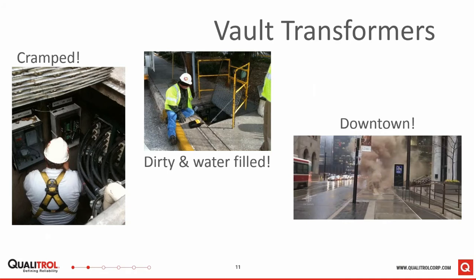Okay. Well, as the picture on the left shows, typically inside a vault it's very cramped. The access is difficult. Most of the time you're going through a sidewalk or sometimes even a manhole that's in the middle of a street. And as the picture on the right shows, when cables fail or transformers fail, the public generally is going to know about it well before the utility because of the smoke and or flames coming out of the sidewalk. So, of course, these are things we want to do our best to avoid.